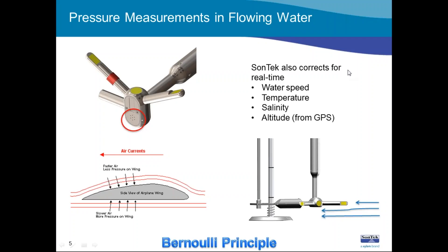As we worked on this project, it became clear that the Bernoulli principle is a huge correction factor. But SonTek also added rigorous corrections for temperature over the full operating range, salinity, and altitude. The altitude at which you're using the sensor affects water density, and water density affects the amount of pressure it puts on the sensor. We can correct for altitude because the FlowTracker 2 has a built-in GPS. All of these corrections together offer a very good solution, and we actually have a patent pending on it.